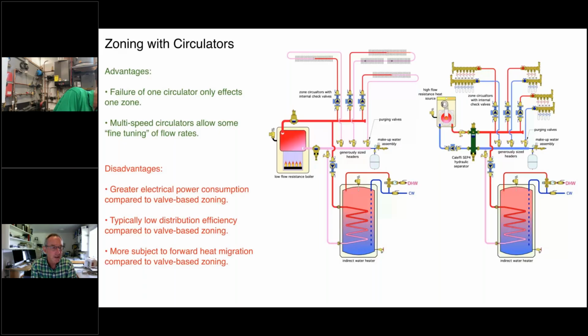Disadvantages, and Hot Rod, I'll read these, but if you have any other comments, jump right in here. But real quick, you're definitely going to use more electrical power with zone circulators, especially the older permanent split capacitor motors that have been around now for several decades, compared to zoning with valves. Yep. Typically lower distribution efficiency compared to valve-based zoning, and that's simply how many watts are being used by the distribution system to deliver the heat on a design load condition. And circulators tend to have lower distribution efficiency. And I put down here more subject to forward heat migration compared to valve-based systems, especially if that check valve, for any reason, gets a little bit of dirt in it, something that doesn't allow the disc in the valve or the flapper to fully seat.